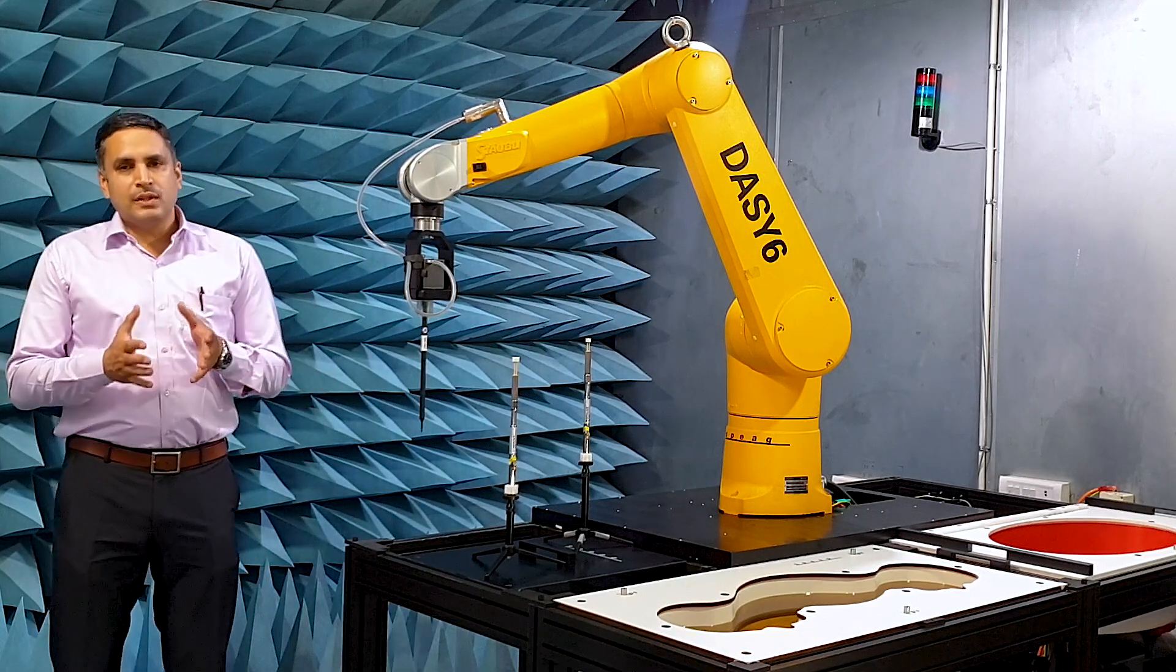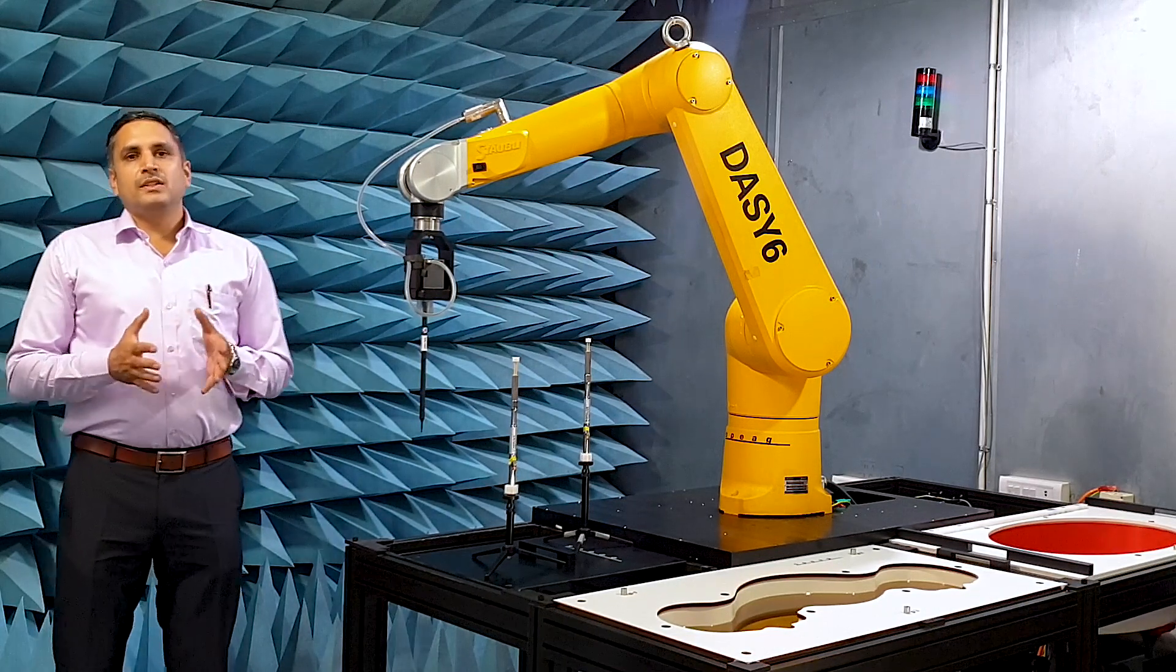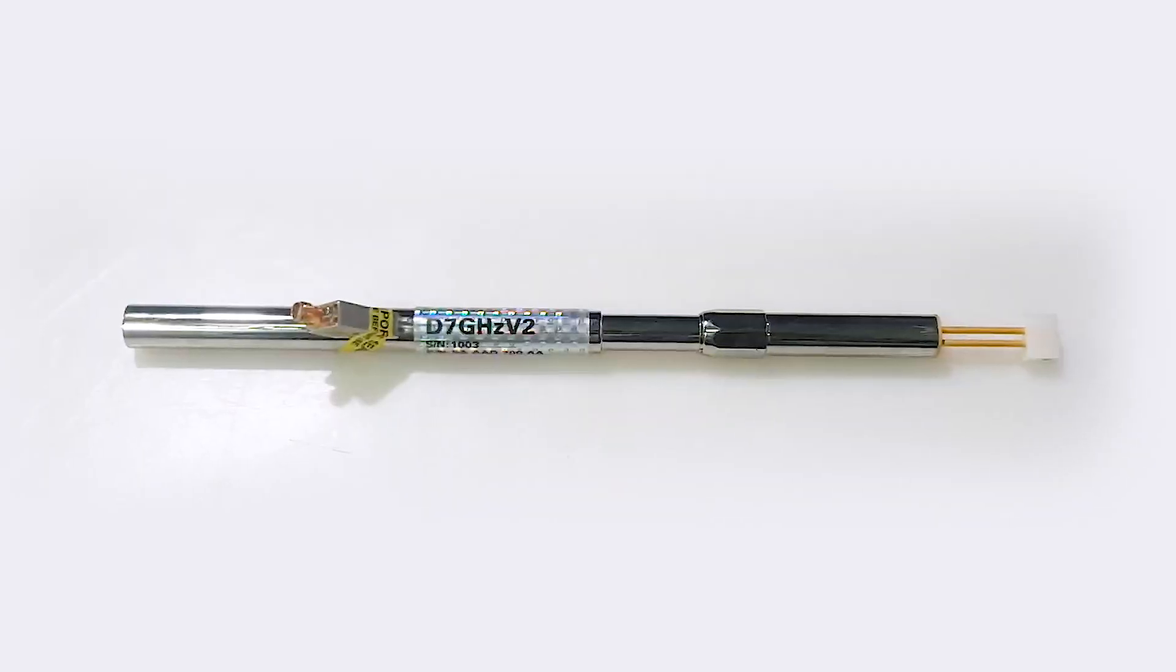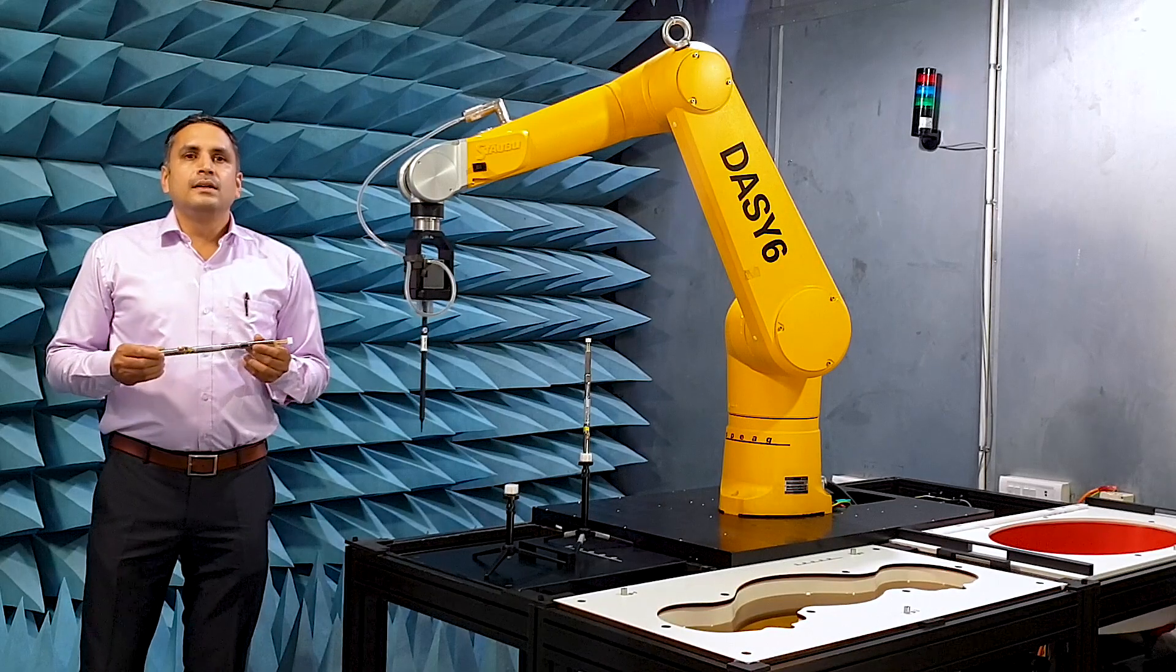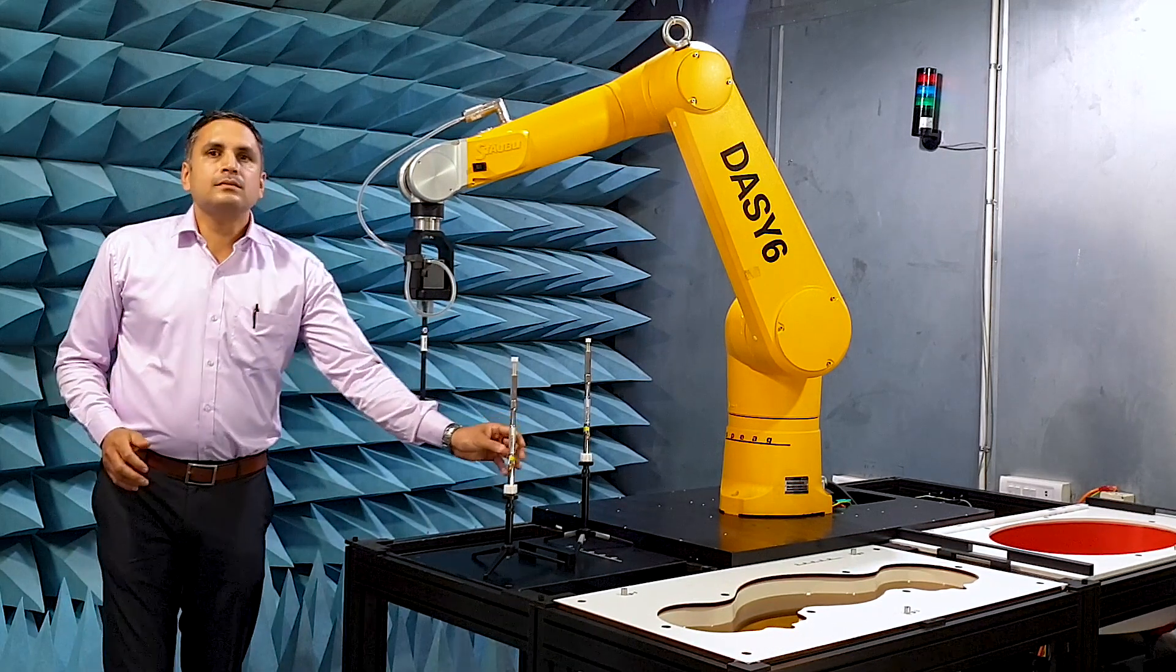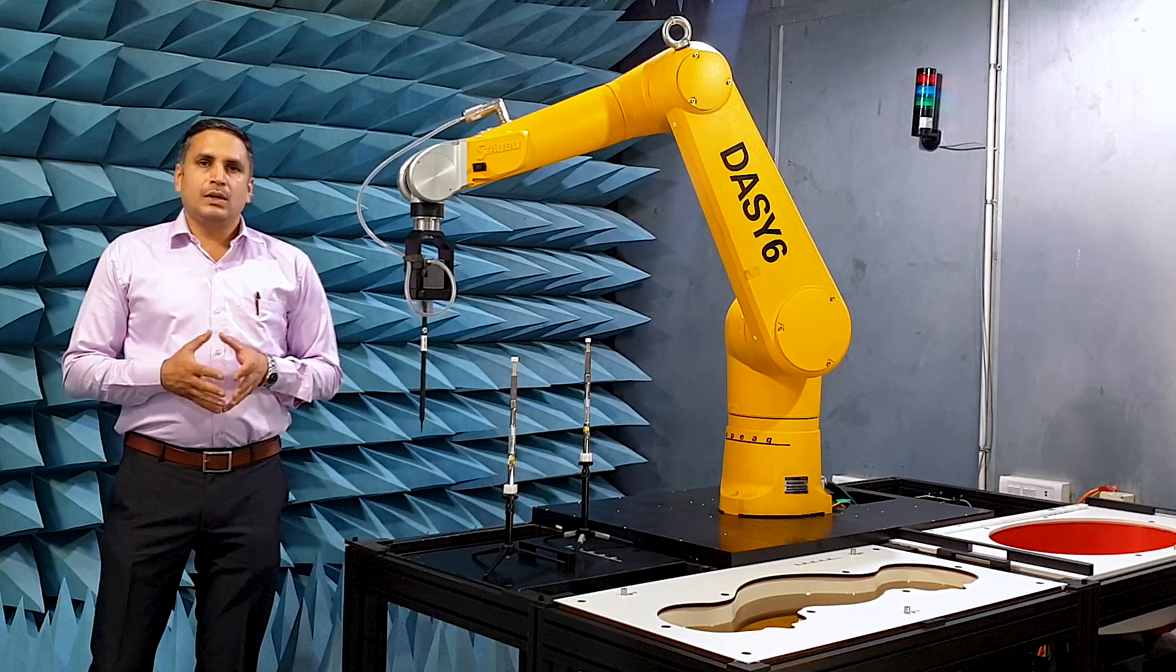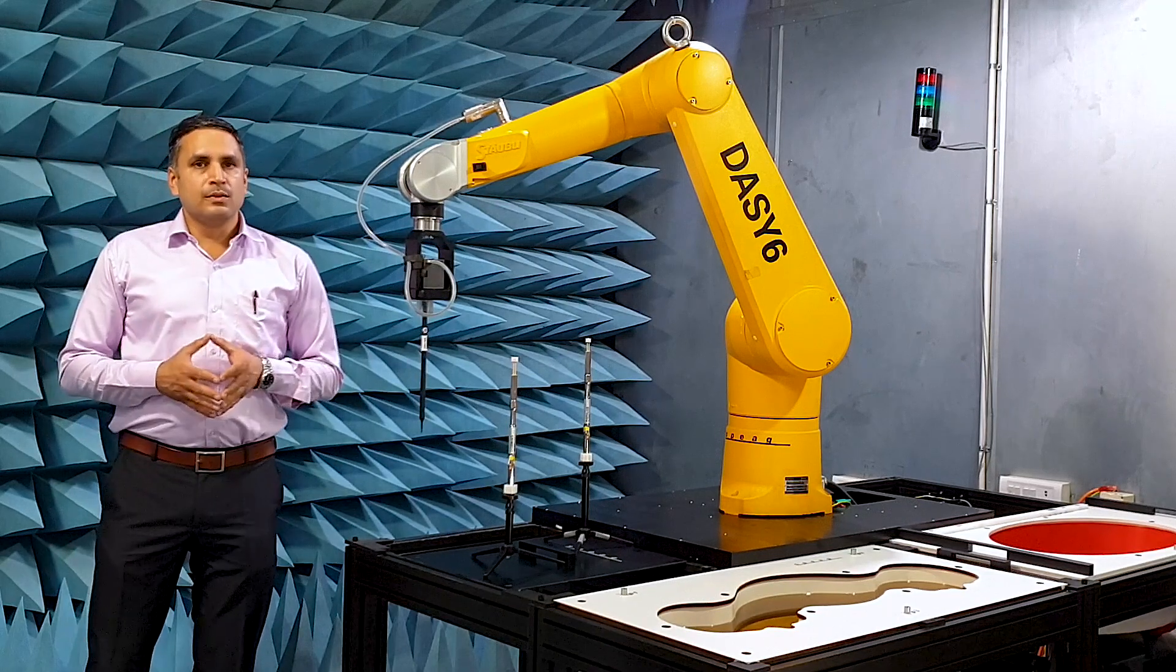Today, I will demonstrate how straightforward SAR and transmitted power density measurements above 6 GHz can be done. For this, I use the 7 GHz system verification dipole that is delivered by Speag together with the calibration certificate that not only includes the calibrated 1 gram and 10 gram values, but also the 1 cm² and 4 cm² transmitted power density values.